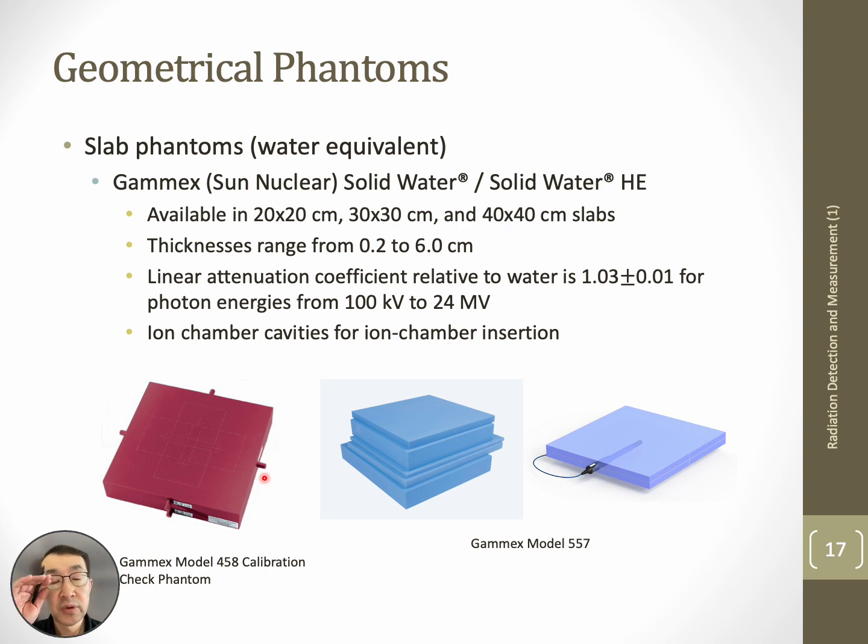This solid water is rather handy because it is cumbersome to set up an actual water phantom every month or every morning to check the output. Instead you can easily handle this phantom. It's a lot simpler. It's easy to move around, and there's no worry about water damage.